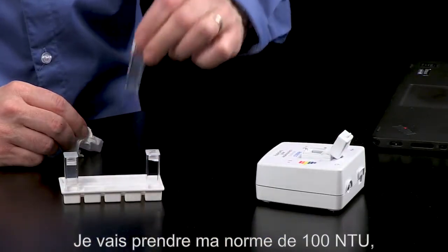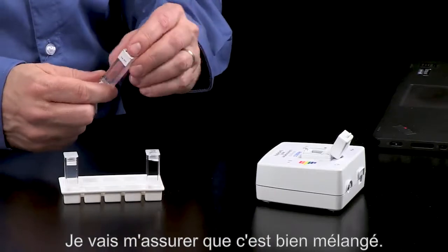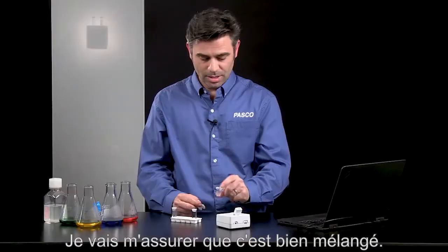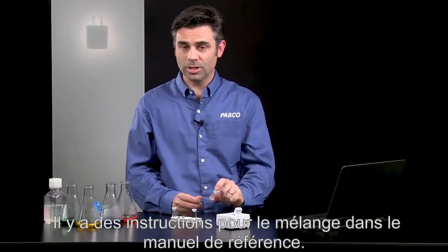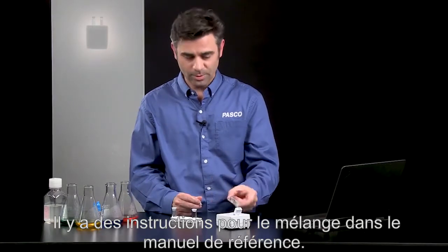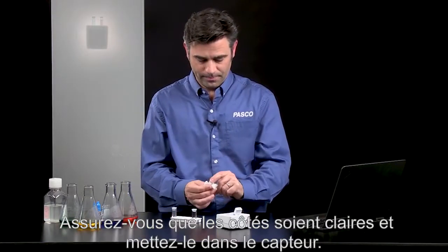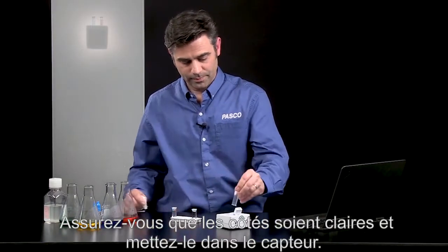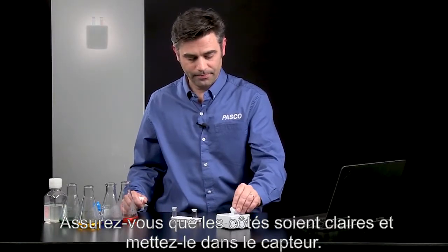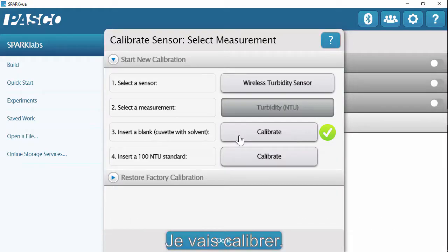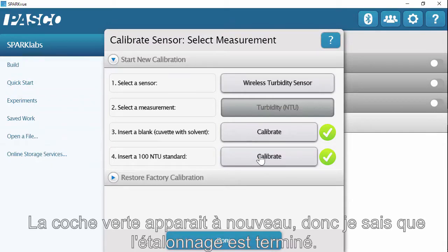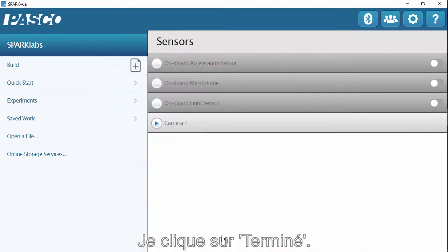I'm going to take my 100 NTU standard. I'm going to make sure it is mixed, and there are instructions for mixing in the reference manual. I'm going to make sure the sides are clear. Put that in. And I'm going to calibrate. I get that check again, so I know calibration is complete. I'm going to hit done.